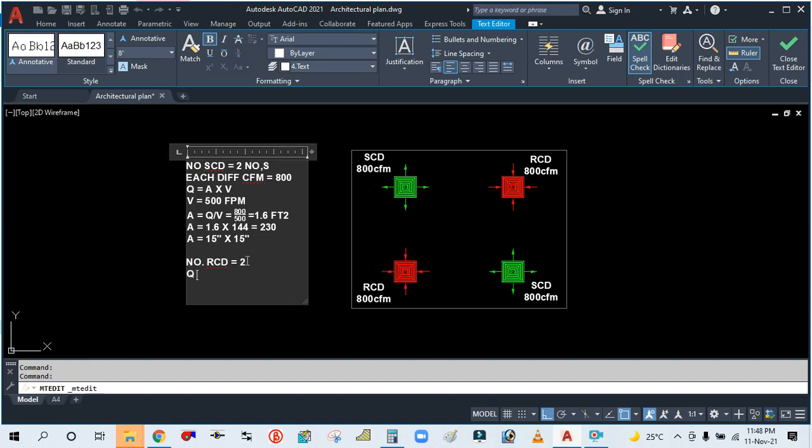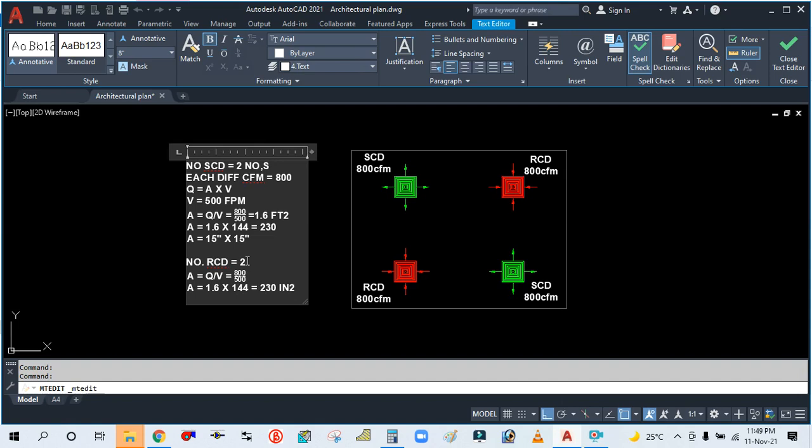So Q is equal to A into V. A is equal to Q by V, equal to 800 divided by 500. So total area we are getting 1.6 square feet, into 144, and then we are getting 230 square inches.